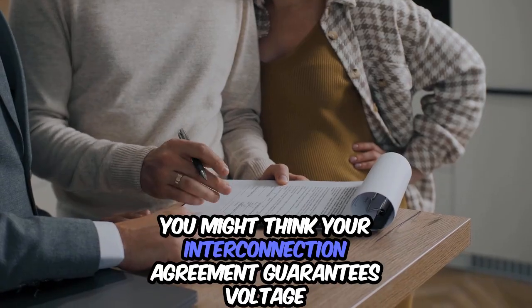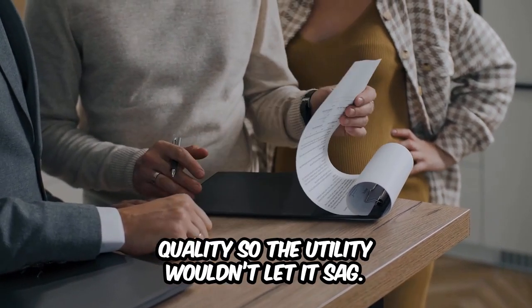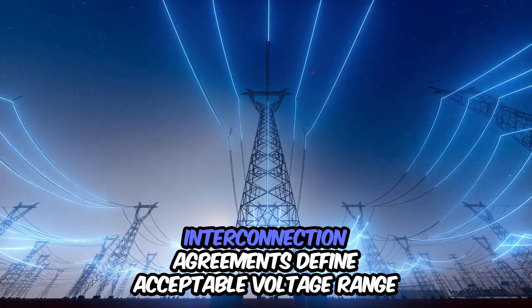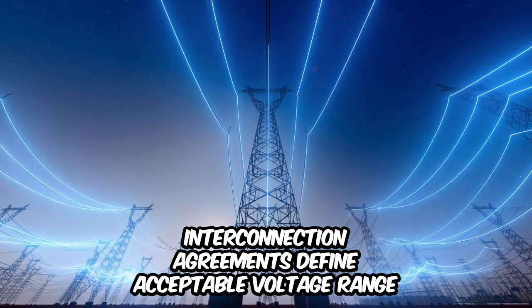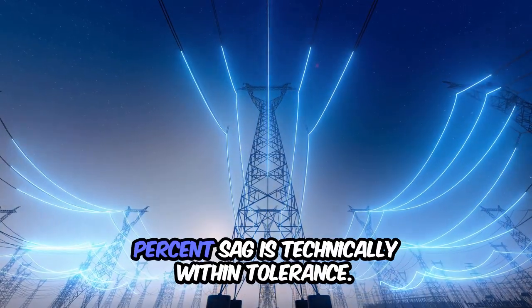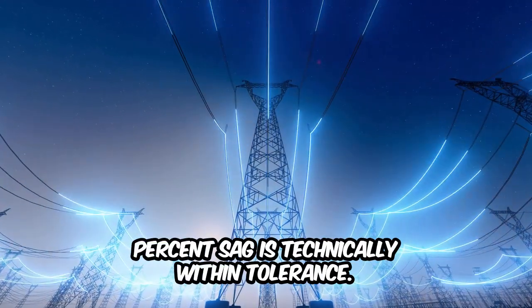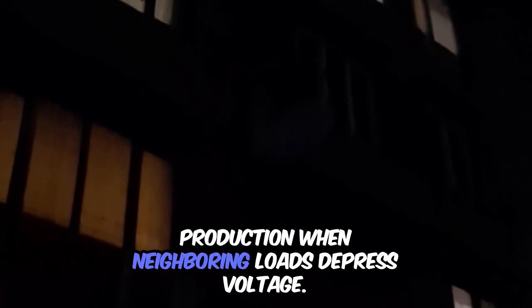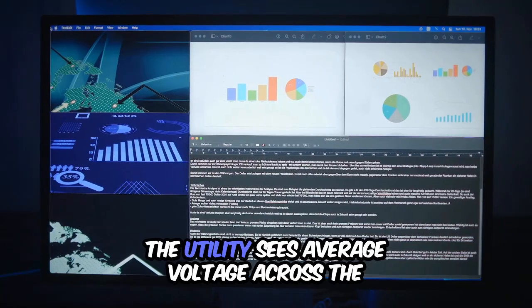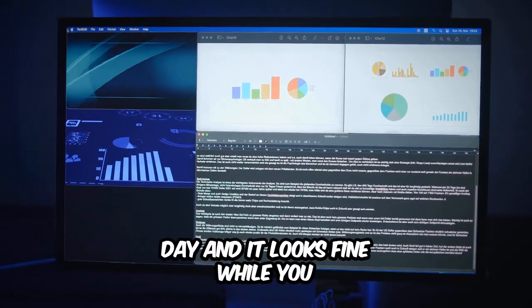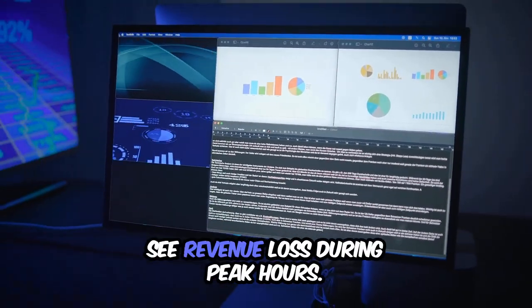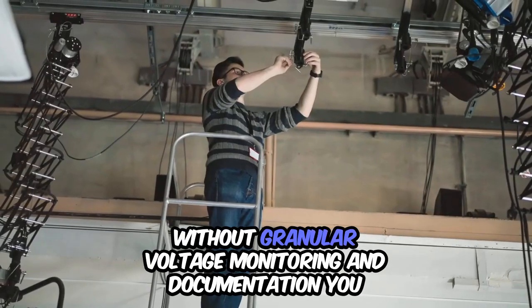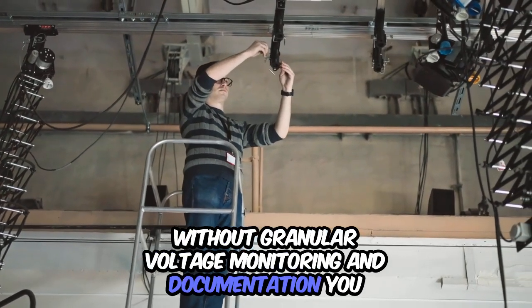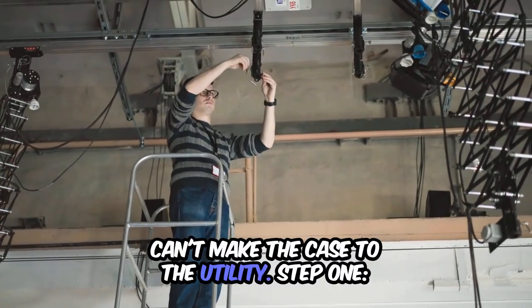You might think your interconnection agreement guarantees voltage quality so the utility wouldn't let it sag. Interconnection agreements define acceptable voltage range, so a 1.5% sag is technically within tolerance. Compliance doesn't mean optimal, and sag often happens only during your peak production when neighboring loads depress voltage. The utility sees average voltage across the day, and it looks fine while you see revenue loss during peak hours. Without granular voltage monitoring and documentation, you can't make the case to the utility.